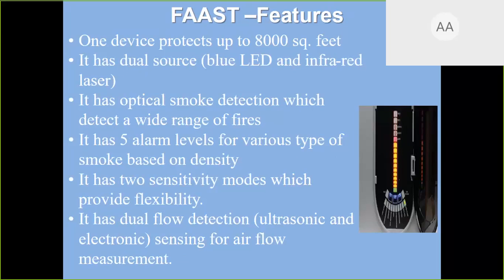Rays come from the device and are detected by any smoke. Any type of smoke, it will give you the alarm. It has dual source, blue LED and infrared laser. It has optical smoke detection, which detects a wide range of fires. It has 5 alarm levels for various types of smoke based on density. It has 2 sensitivity modes, which provide flexibility, and it has dual flow detection, ultrasonic and electronic sensing, for airflow measurement inside the duct. It will measure the airflow, and if anything is sensed beyond the design capacity, it will give you the alarm.